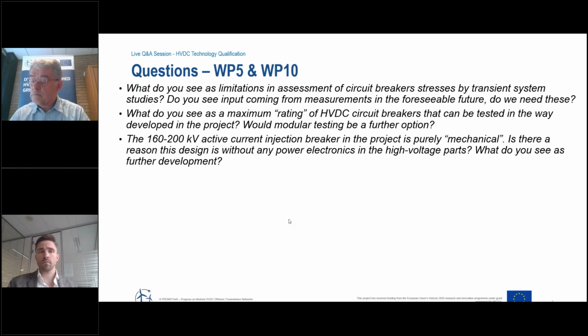So the advantage of the mechanical breaker is that it is designed with a vacuum interrupter, which is well proven for more than 20 years at transmission voltage up to 200 kV. Also, for the mechanical breaker, I think there is a significant cost benefit as compared to the HVDC circuit breaker technology applied with many power electronic devices such as IGBT. So that's my comment.